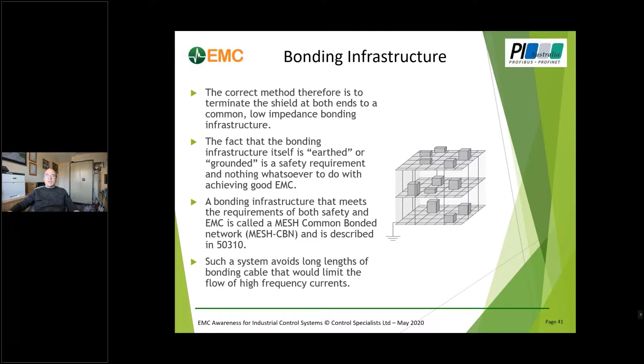They don't affect the flow of fault currents, but they will affect where these high frequency currents are going. And if you remember, the uncontrolled flow of currents flying around is the biggest issue. So there are things we can do in the panel design.